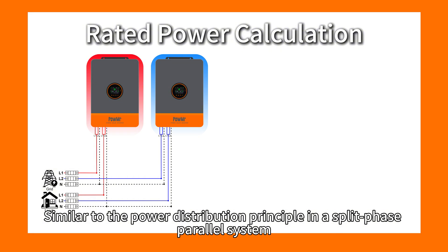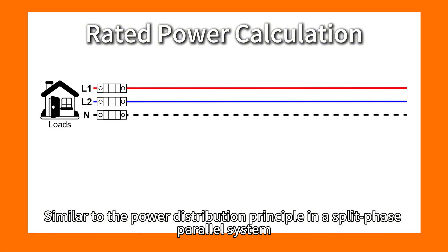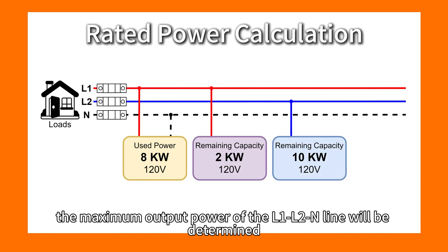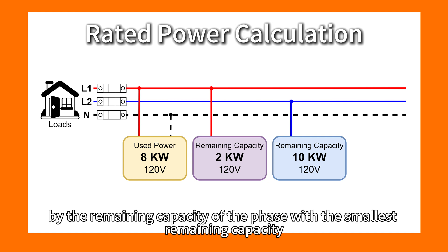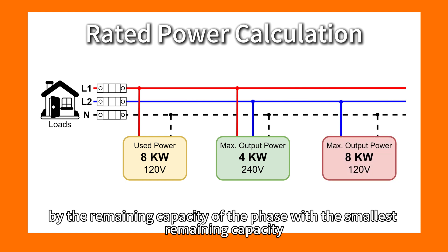Similar to the power distribution principle in the split-phase parallel system, if an 8kW load is connected to the L1-N line, the maximum output power of the L1-L2-N line will be determined by the remaining capacity of the phase with the smallest remaining capacity.